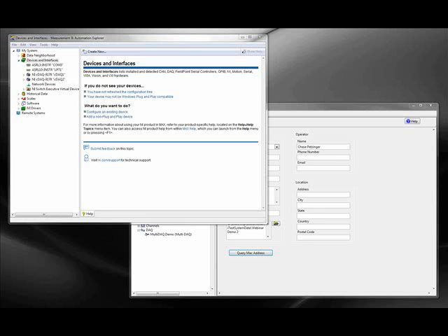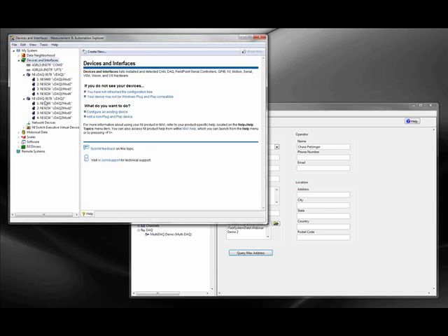All right, so starting things off, I'm going to hand it to Todd Holkamp here, who's going to begin our demonstration. I wanted to quickly show you in the Measurement and Automation Explorer software, we have two chassis currently hooked up, two 9178 8-slot USB chassis. They both have a synchronization card, the 9469, that allows for the synchronization of all the channels in one task. And we have three 9234 modules used for acceleration-based measurements.